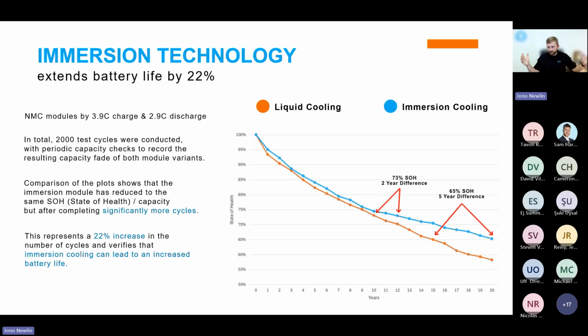So let's think about that in a deployed system. If liquid cooling is, say, at 10 years - again, state of health really can vary based on usage and environment, so let's not get into all those details - but if we see a 73% state of health at 10 years for liquid cooling, with this metric we can see an elongation of cycle life by about 2 years, effectively gaining 2 years of performance with an immersion cooled system. And going further, at 15 years for liquid cooling to reach the same state of health, you gain about a 5-year difference.